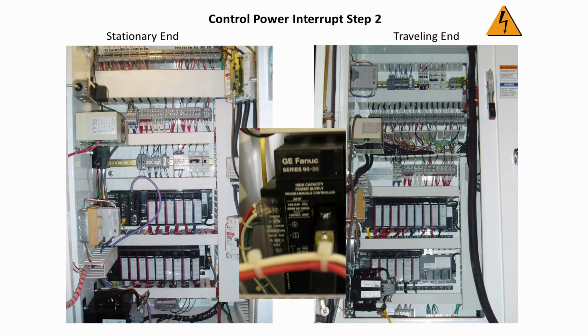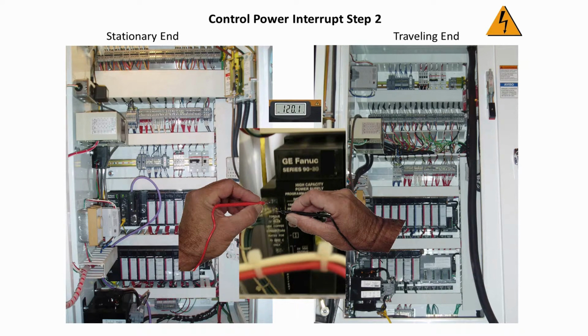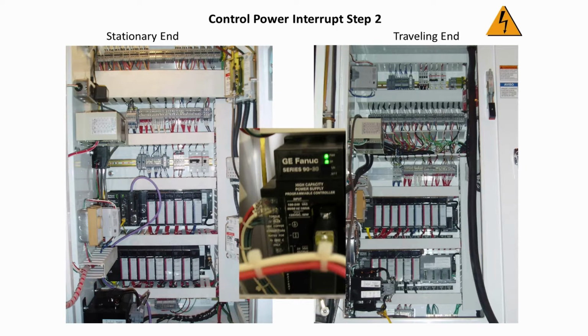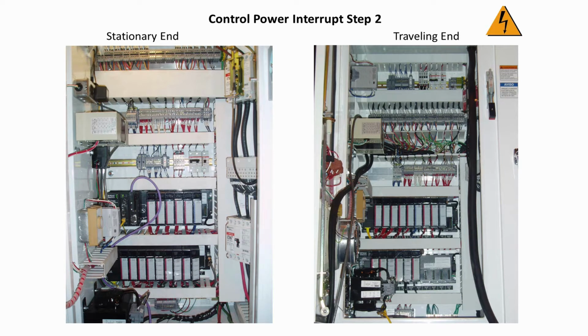Check number 2. If one of the power supplies does not have any lights on, check for 120 volts on the power supply. If you have 120 volts, then replace the power supply. Check number 3. If the power and OK lights are on and the run light is not, then move to the top PLC rack on the stationary end. You will see a key that is in the CPU next to the power supply. Cycle the key twice by quickly moving it from off to on, off to on. If the run light comes on, the saw is ready to be placed back into production.